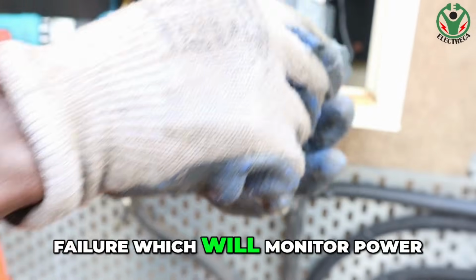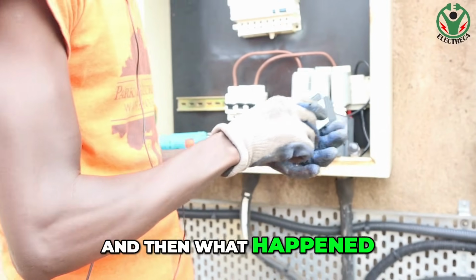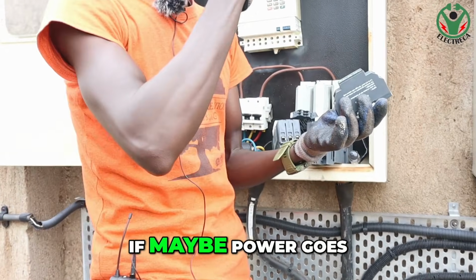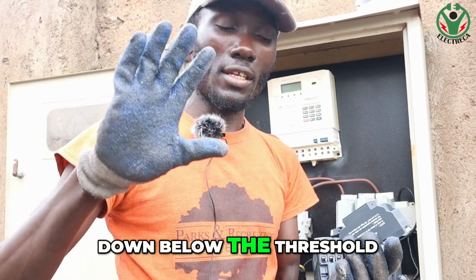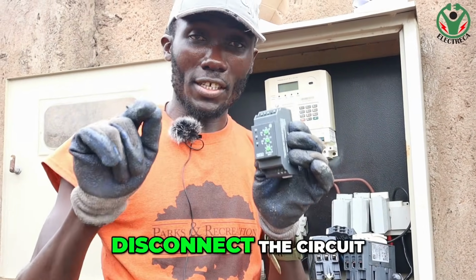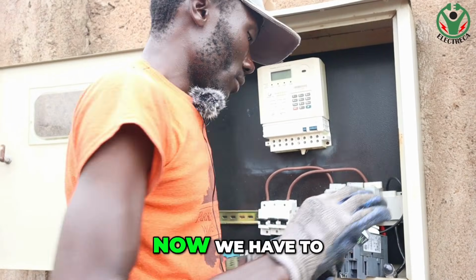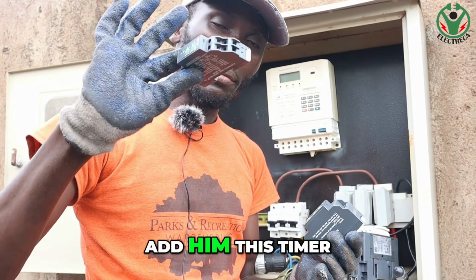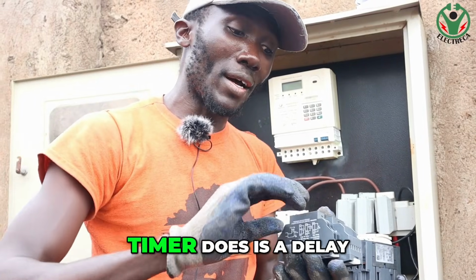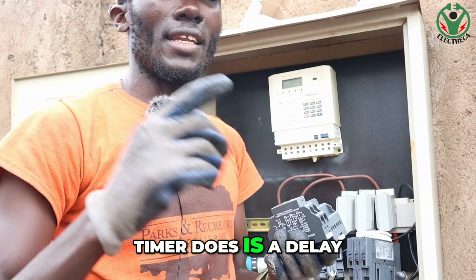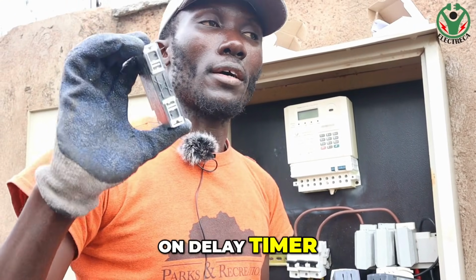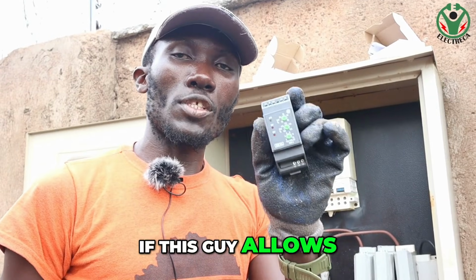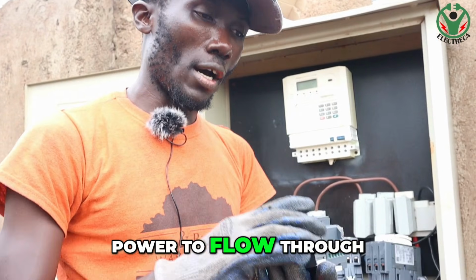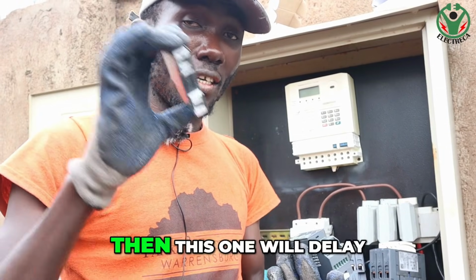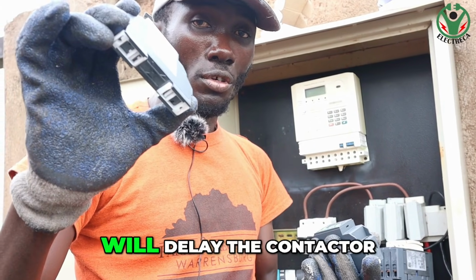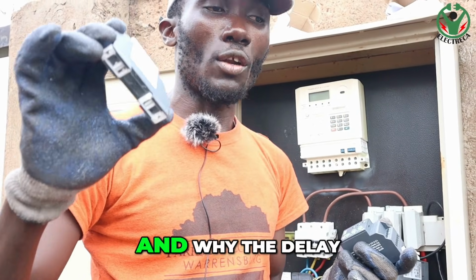The phase failure relay will monitor power. And then if power goes down below the threshold, this guy will disconnect the circuit, okay? Now, we have to add this timer here, and what the timer does is a delay. So this is an on-delay timer. If this guy allows power to flow through the circuit, then this one will delay the contactor to engage.